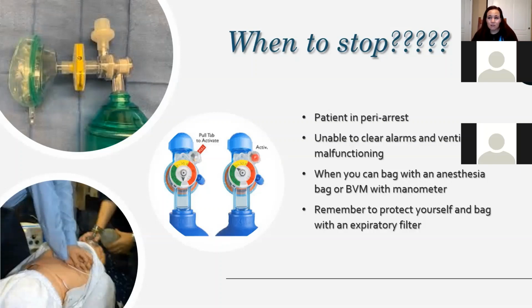I've tried to do this several times. It's really rough. Whoever is doing CPR really has to pay attention to the ventilator, because you have to time those things just like you did the old school CPR. You have to time those things in order to not overwhelm the vent and keep getting those high pressure alarms. But those have been some of the recommendations from the CDC, to try and keep your patient on the ventilator while you're resuscitating during CPR.